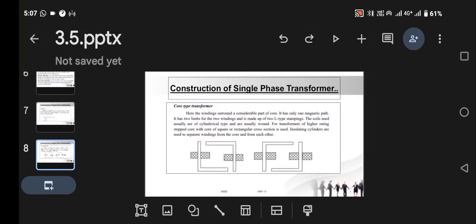First, we will see the core type of transformers. The core type of transformers looks like this. It has only one magnetic path. It has two limbs for two windings and is made up of two L-type stampings. The coils used are usually cylindrical type and are usually wound. For transformers of higher rating, a stepped core with square or rectangular cross section is used. Insulating cylinders are used to separate the windings from the core and from each other.